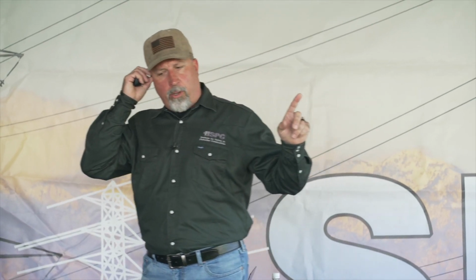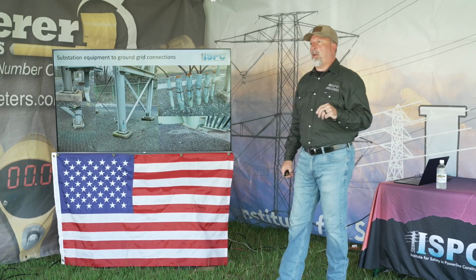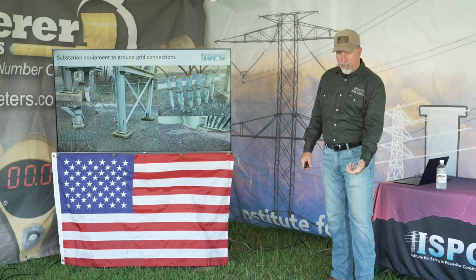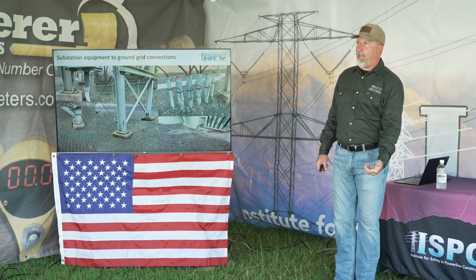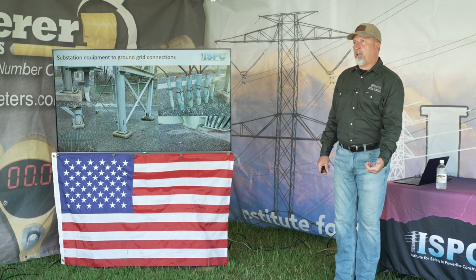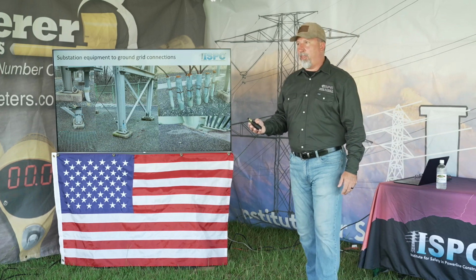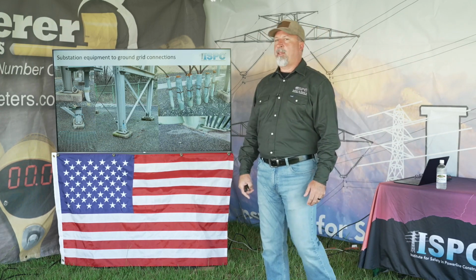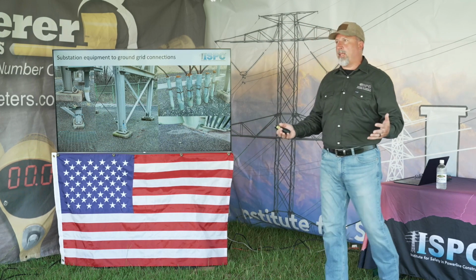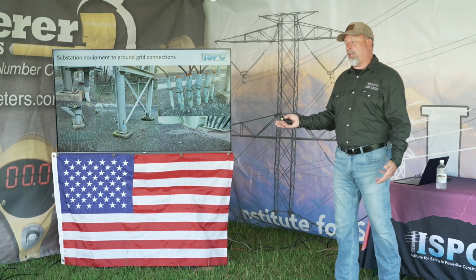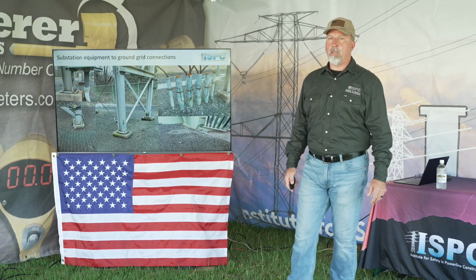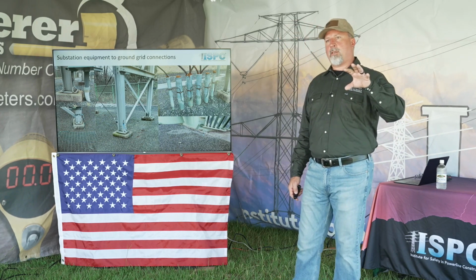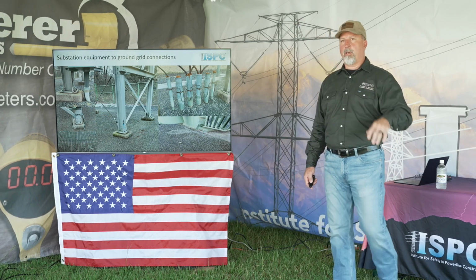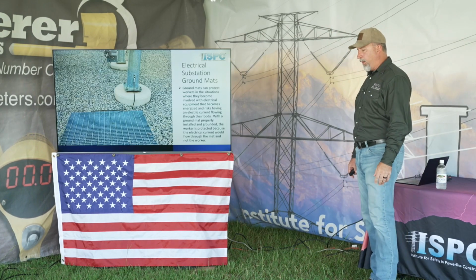Looking at those ground tails, some of those pictures you saw from the 500 kV yard substation, I have personally taken an amp clamp and measured 47 amps on that ground pigtail. So not only are they eliminating a current carrying path, but if conditions happen to be right when they cut these things, they could potentially get killed.